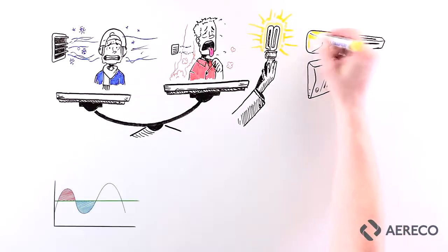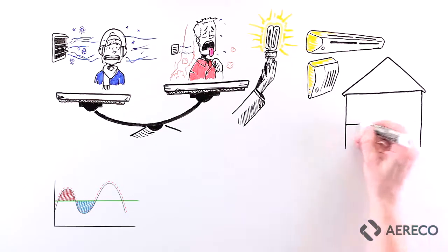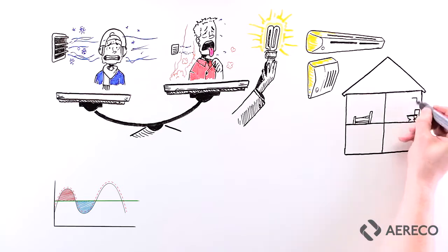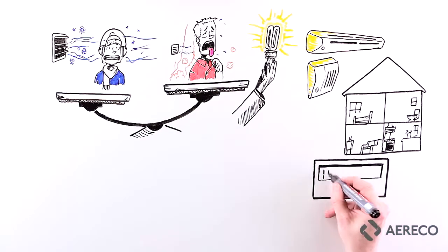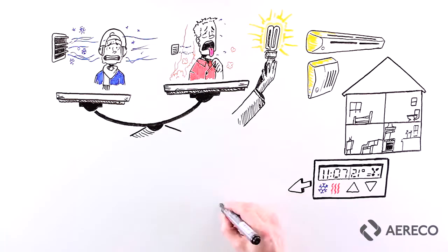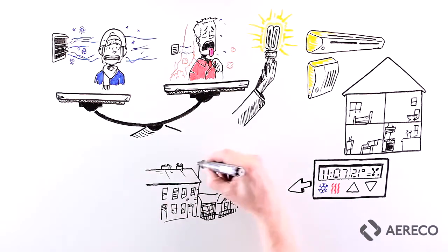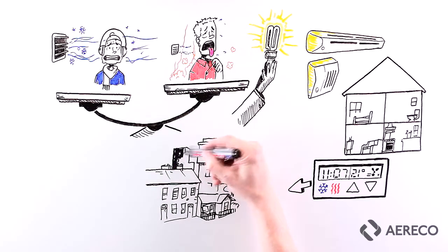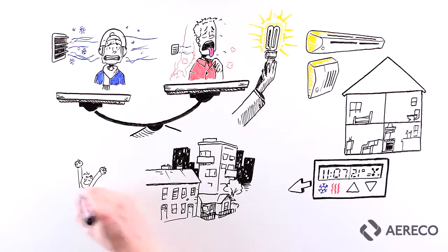Demand control ventilation, or DCV, is a way of adjusting ventilation automatically according to demand, with sensors that measure air quality or need, in every room, in every dwelling, at any time. This approach is as logical as controlling your heating with a thermostat, and can be applied to many systems, from passive stack ventilation through mechanical extract systems to MVHR, in individual homes and collectively in multi-family buildings.